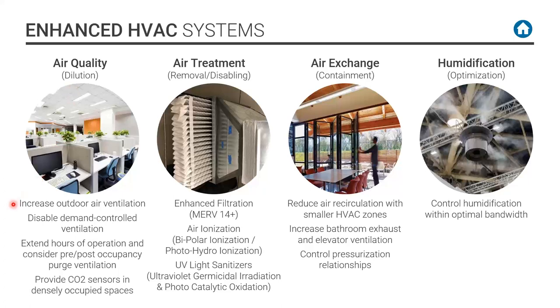So in a building, we want to increase outdoor air ventilation. If we have demand control ventilation in a building, and I'll describe what that is, you want to disable it. Demand control ventilation is an energy conserving system, which is very logical. It says if you have fewer people in the building, you should bring less outside air in, because the way we've designed buildings in the past is the amount of outside air you bring in is based on the number of people and the activity. And we have carbon dioxide sensors to save energy. We're saying now during this pandemic, until there's a vaccine and we've gone through this, let's disable the demand control ventilation so we maximize the amount of outside air you bring in. Extend the hours of operation to consider pre and post occupancy purge. We're suggesting 2 hours before and 2 hours after occupancy that the system is bringing in outside air to dilute what might be in the air.